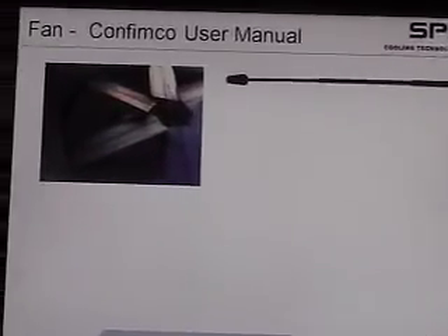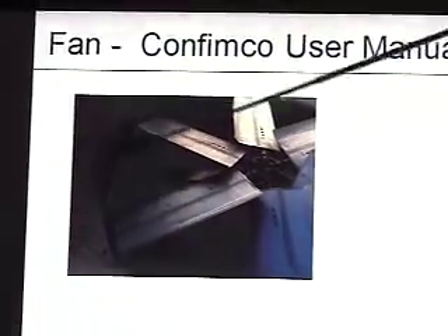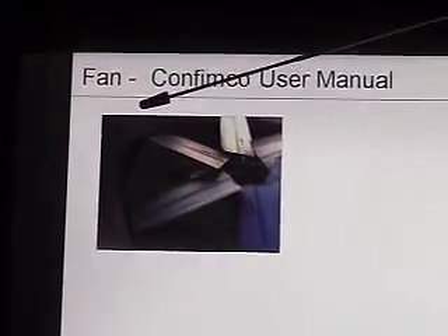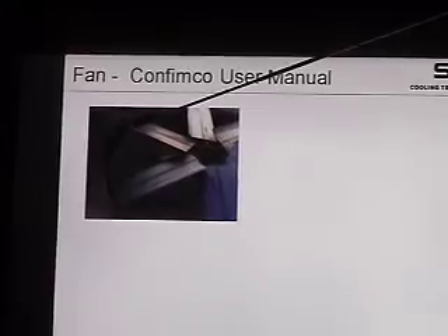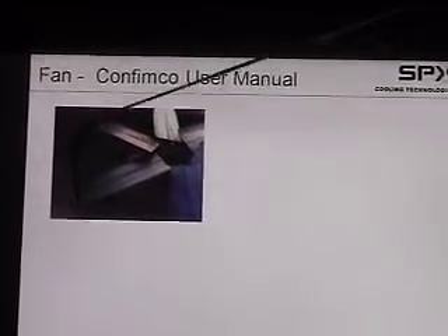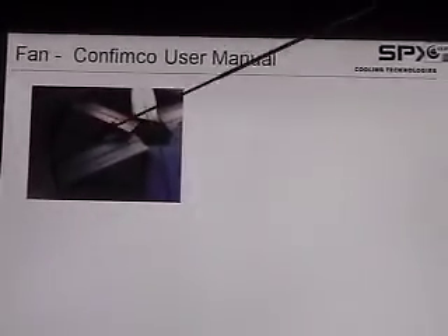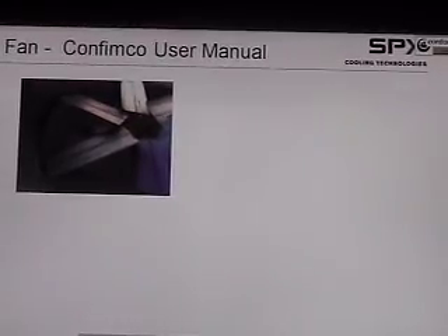Our fan on this tower is a Confimco fan, and there is a user manual for it. And basically there's a bushing there with the bolts, and then the fan blades that can be individually pitched. And then you just want to make sure that the spacing here, the tracking is the same up and down, and from the tip of the fan blade over to the fan cylinder, that it's the same for all the fan blades.